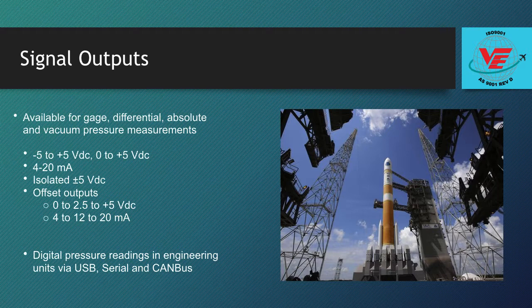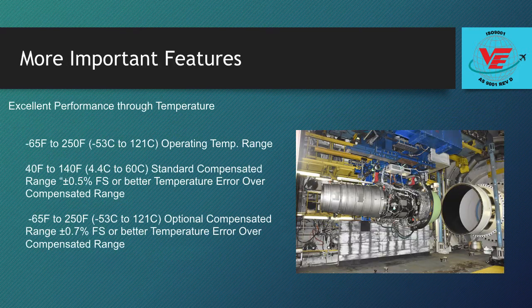Finally, there are new variants of the P895 with digital output capability, USB, CAN bus, and serial output options, where pressure, temperature, calibration data, as well as the ability to set zero and span can all be done digitally. The P895 can operate at temperatures of negative 65 degrees Fahrenheit to 250 degrees Fahrenheit. We offer two options for temperature compensation. The standard is 40 degrees Fahrenheit to 140 degrees Fahrenheit, and an optional custom range within the operating range of the sensor.